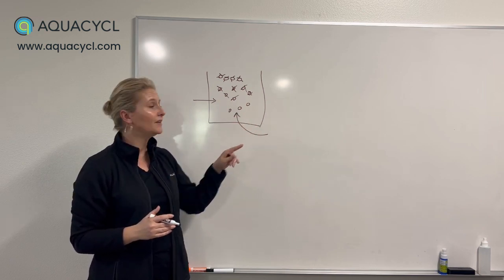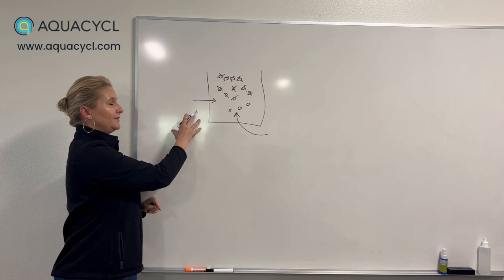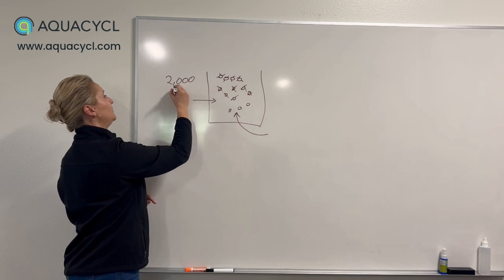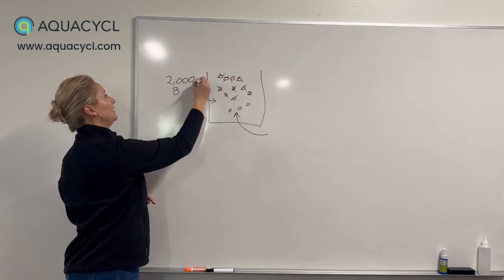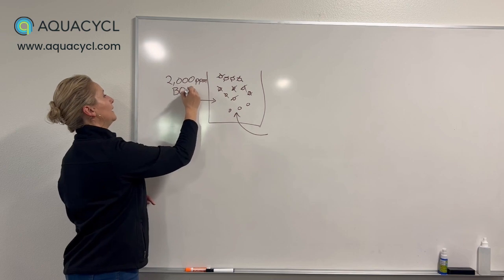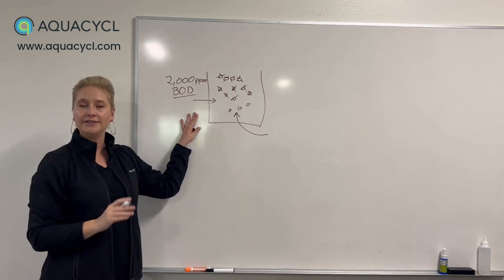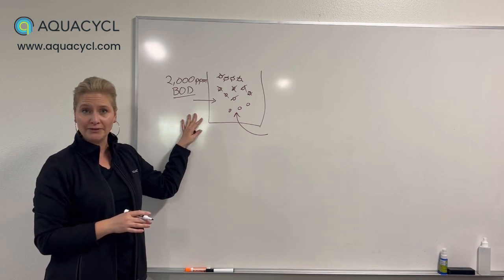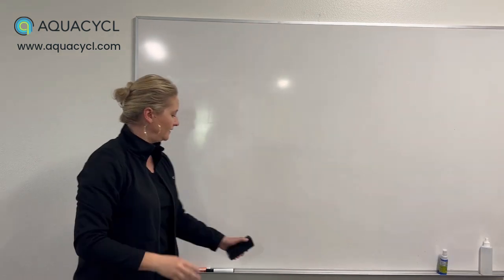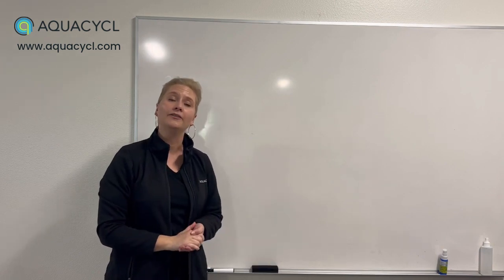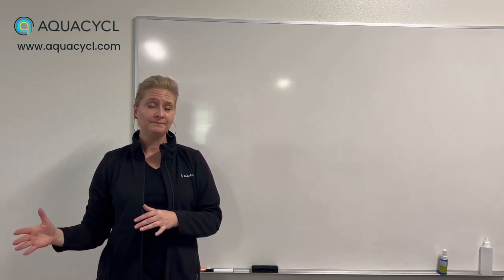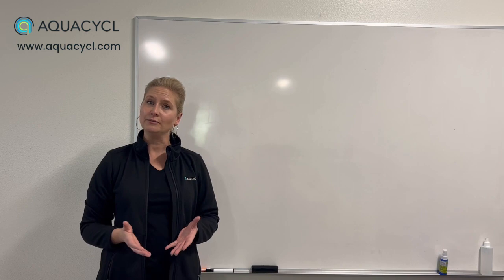So when you get into aeration technologies, you usually want to limit your inflow to 2,000 parts per million, or milligrams per liter of biological oxygen demand. That's your limitation, roughly, for aeration, depending on the type of aeration that you're using. Lower is better, it's more efficient and smaller. When you're dealing with a concentration that is higher than 2,000 parts per million of biological oxygen demand, now your options are more on the anaerobic side. So that means no oxygen present in the treatment process.